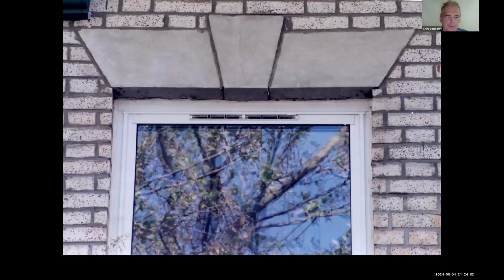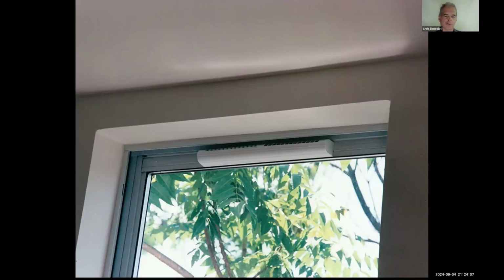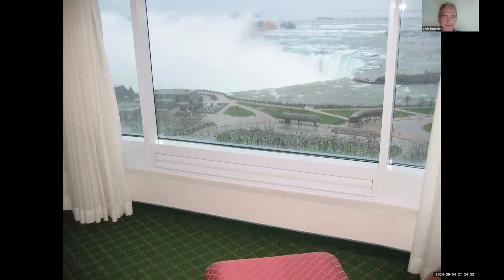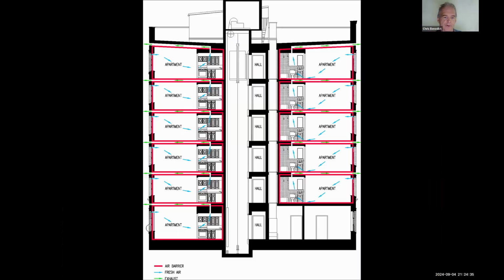A little better is you put a trickle vent in a window. So this is the outdoor view. This is the indoor view of a trickle vent. It has these little grills that put the air outwards and upwards toward the ceiling, and there's a little moving piece in there which moves if wind tries to move too much air into the house, more than 25 or 30 CFM for most models, it'll close. If you have a very airtight apartment building or hotel, these are a good idea. With operable ones, people can close them, which generates phone calls.